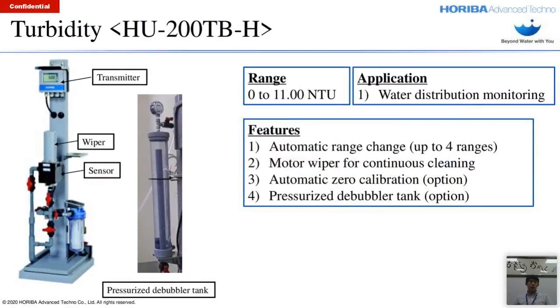Okay, so this is the last parameter for the H1 series. For turbidity, we have HU200TBH. Some of the features include automatic range change, where the transmitter will detect the sample and change the measuring range accordingly to the optimal range. This is a very convenient function. For point number two, we have continuous cleaning for the measuring cell with a motor wiper. As you can see, the wiper is just above the sensor in the picture on the left.